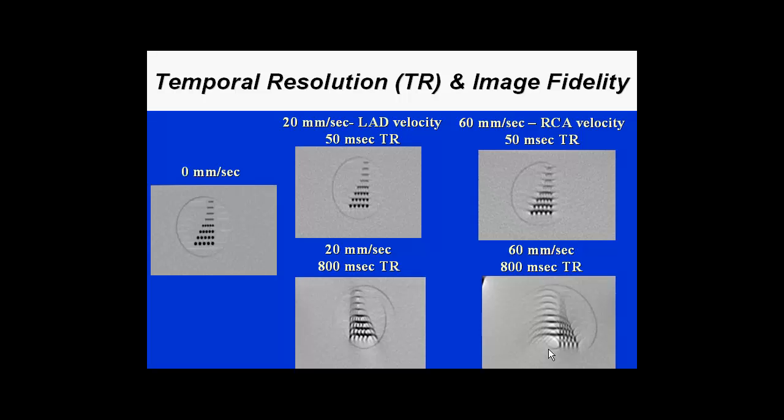On the far right is an example of moving the resolution phantom at 60 millimeters per second, which is roughly the peak velocity of the proximal and mid-right coronary artery during a standard cardiac CT examination. At a 50-millisecond temporal resolution, there is clearly some blurring, but we can still define reasonably down to the medium-sized resolution areas. However, at 800-millisecond temporal resolution, true aliasing of the images comes in. This is very similar to what we see in echocardiography when switching from blue to red in Doppler velocity panels, or like an old movie where a wagon wheel moves so fast it appears to be moving backwards.